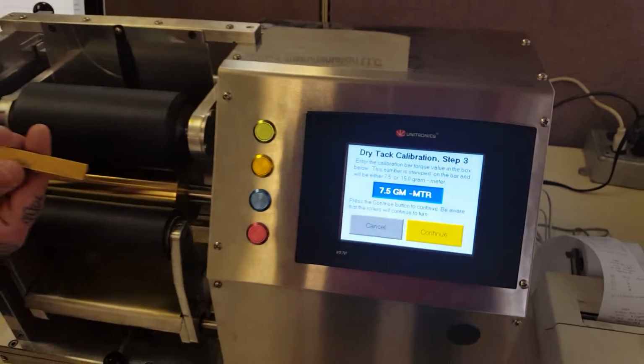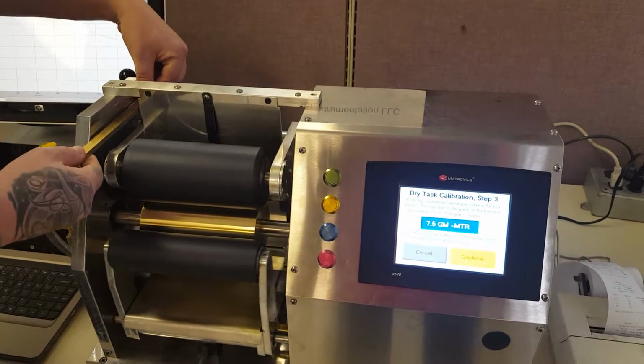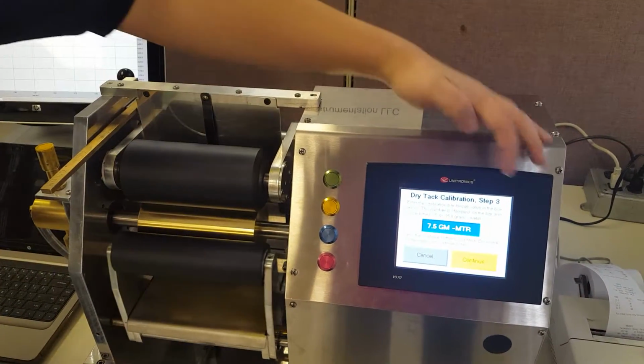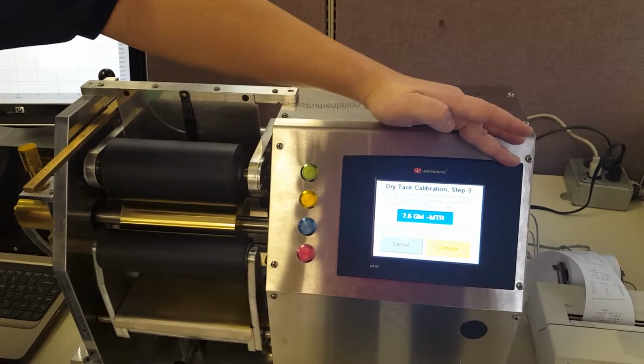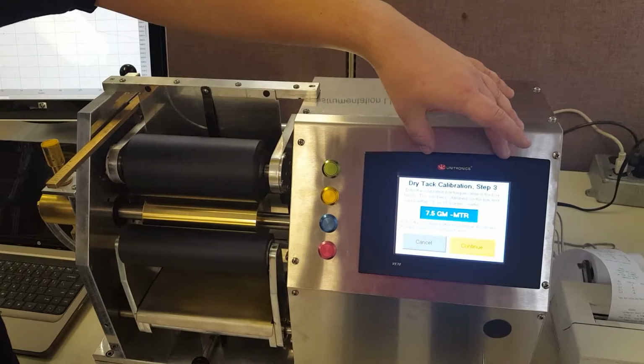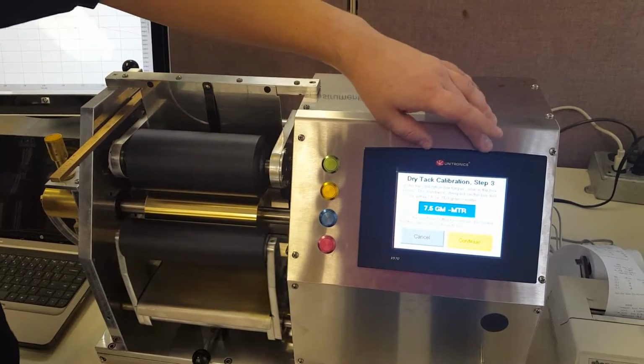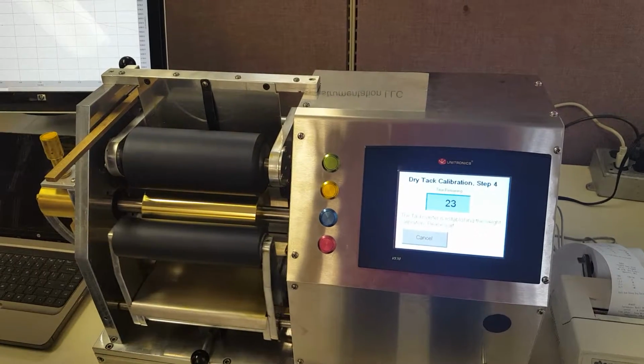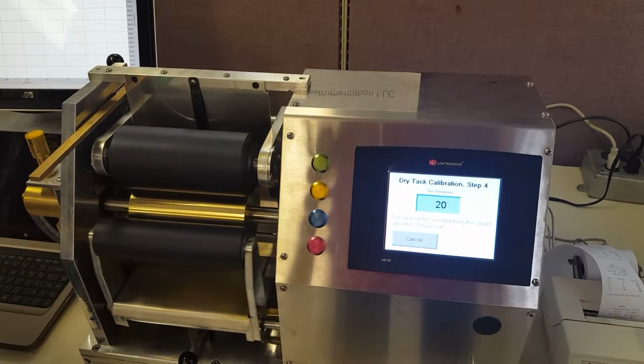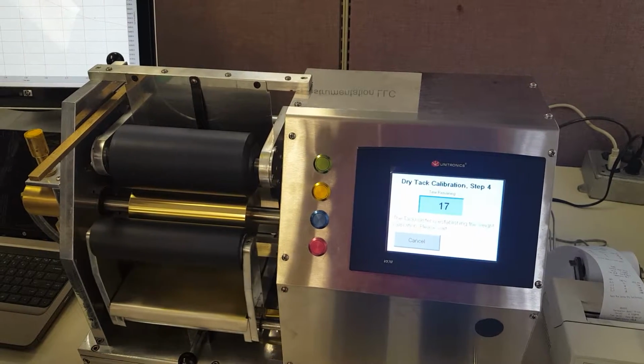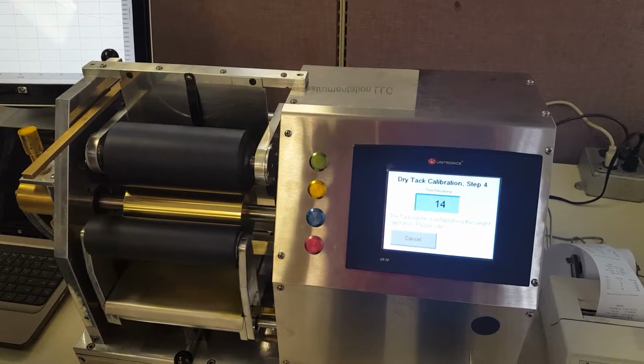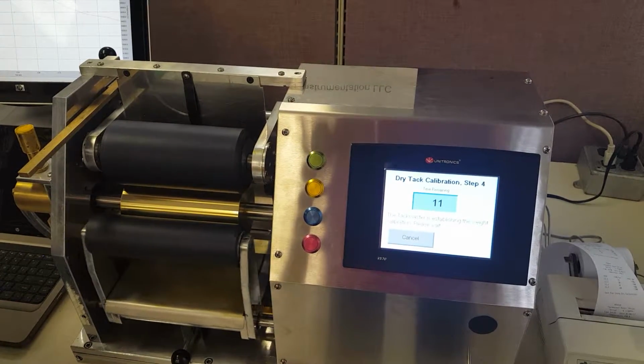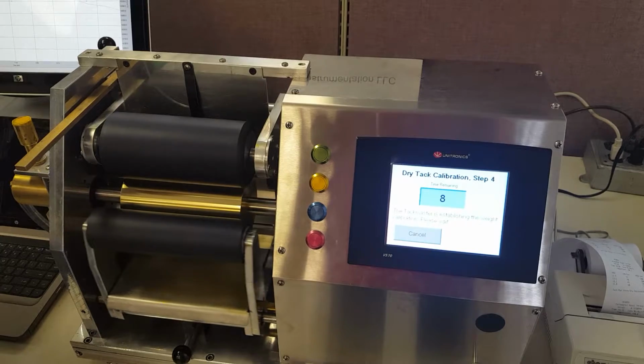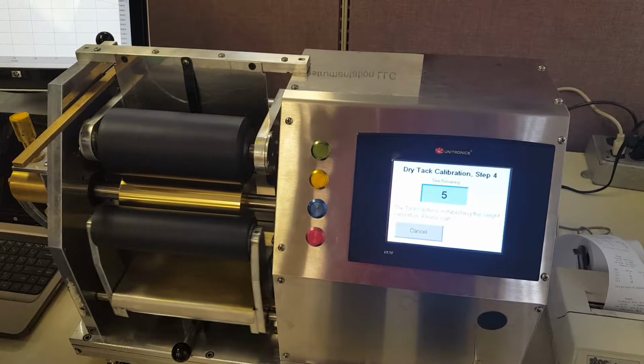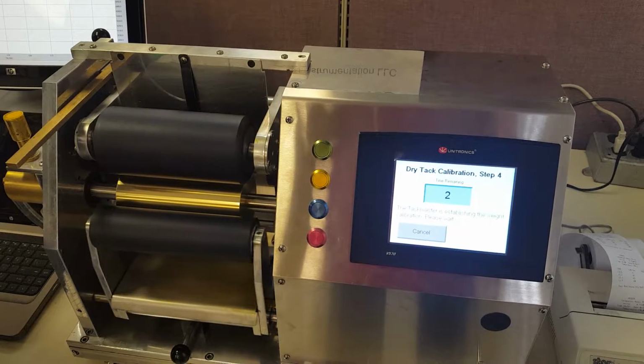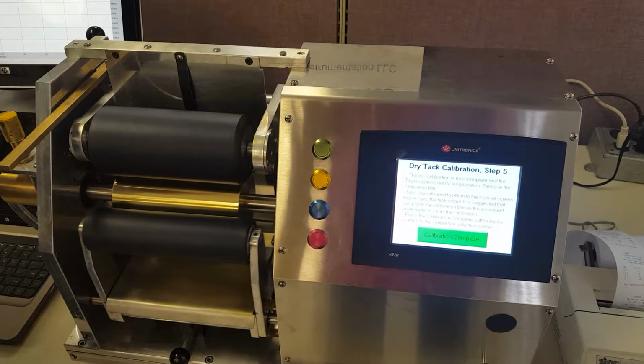Now taking our calibration bar, I'm going to place it here on our calibration saddle, and I'm going to hit the continue button, which, for all intents and purposes, runs a mock test, using our bar to simulate a tack rating. So now this is going to count down for 25 seconds, another parameter that was established in our setup screen, and as this runs, our device is establishing a position in the sensor that's telling us that this particular weight is 7.5 gram meters, and that's the number it's going to be looking for when this particular weight is assigned to this machine. Now as this counts down, our calibration is complete.